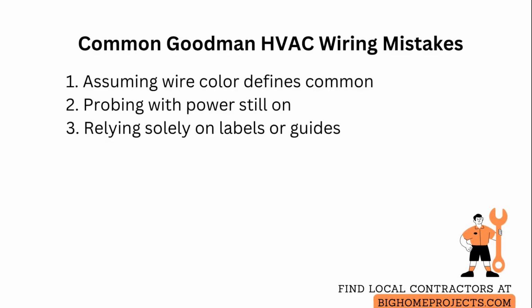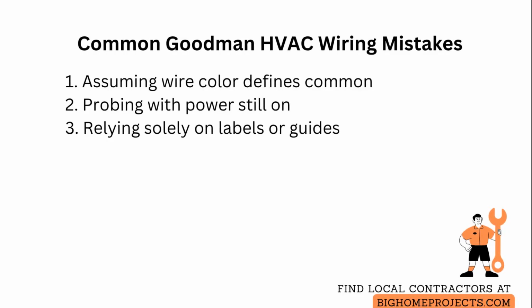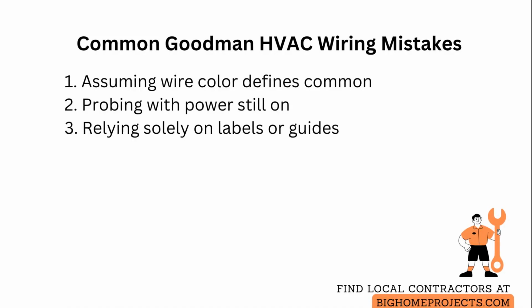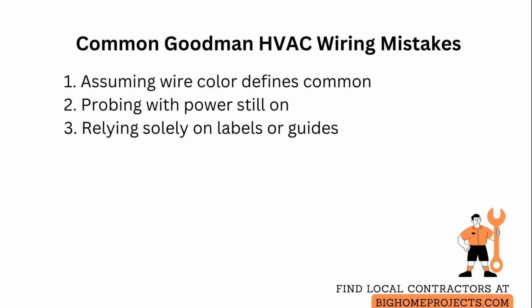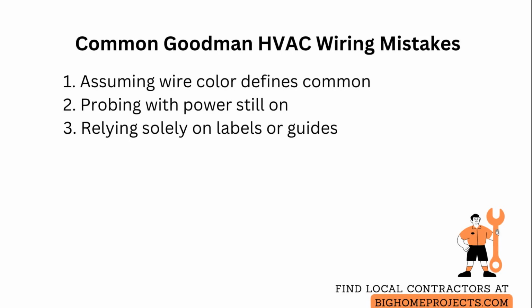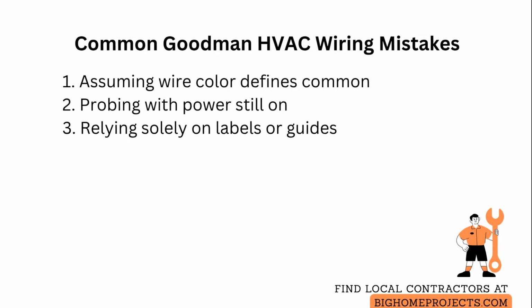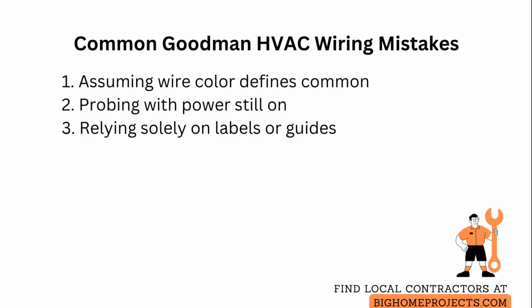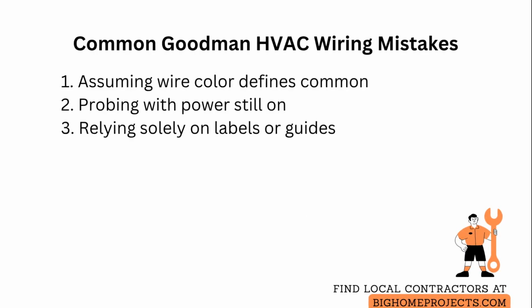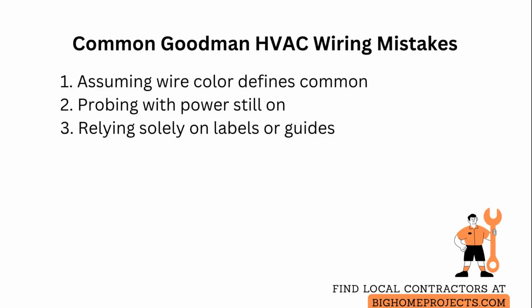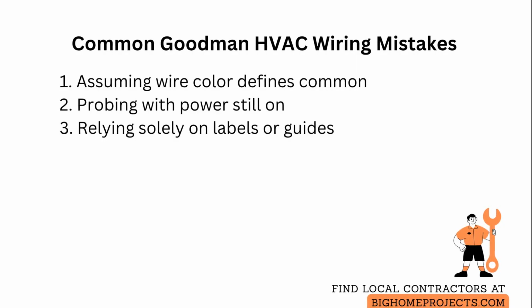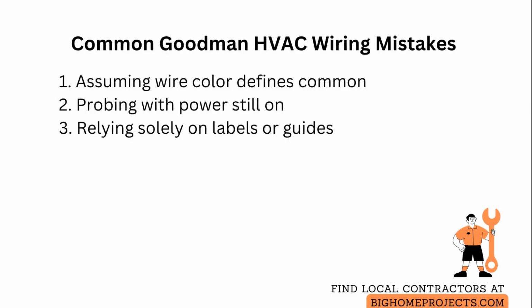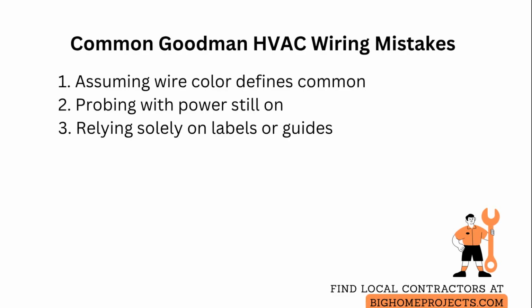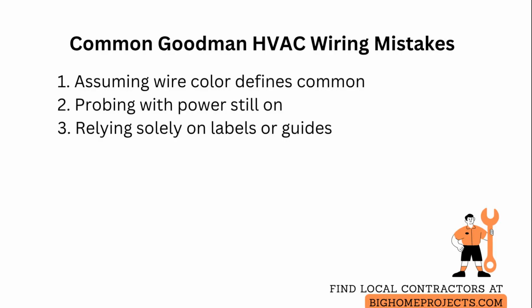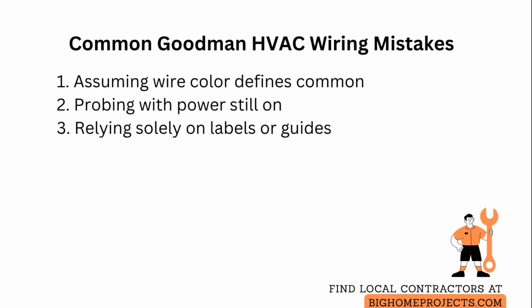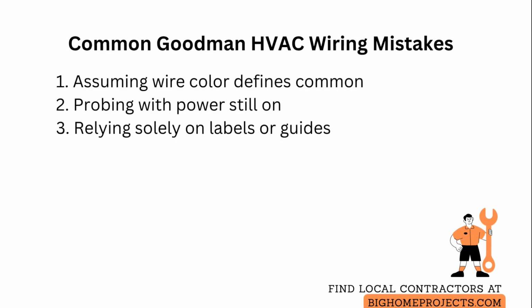Common mistakes start with assuming wire color defines the common and then connecting a wrong conductor. Avoid this by testing every wire regardless of color. Another frequent issue is failing to isolate power before probing, which risks shorting circuits or damaging controls. Always confirm power is off with a meter and follow lockout procedures. A third problem is relying solely on visual labels or aftermarket thermostat wiring guides, which may not match the unit. Always match your measured voltages to the furnace schematic and verify continuity to the transformer common terminal to be certain.